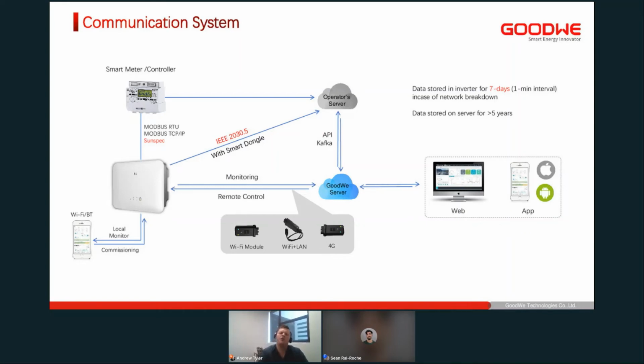We then also have an option for installers that have a lot of our products and want to use their own platform, using an API, pulling data from our platform and displaying it on your own. And then we've also got Modbus RTU, Modbus TCP/IP, and SunSpec, which allows you to use a third-party meter or controller if you'd like. But as I said earlier, we do have a GoodWe GM1000 meter included in the box anyway, so it's not necessary. And then the IEEE 2030.5 with our smart dongle is a requirement for our American customers, but something that we don't see typically in the EMEA region.